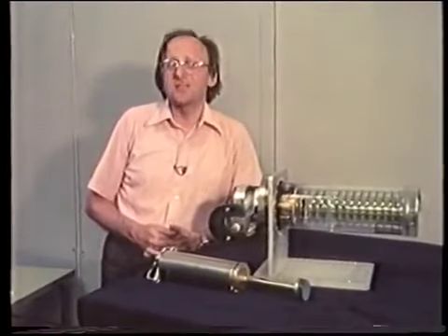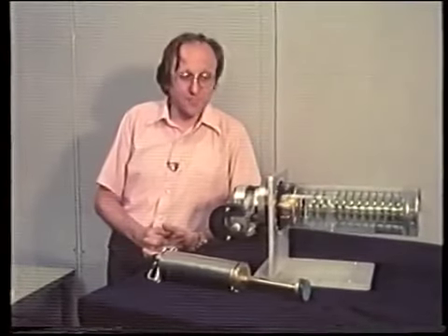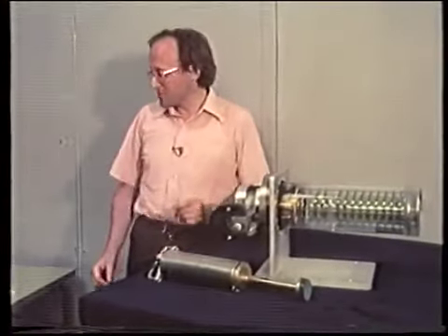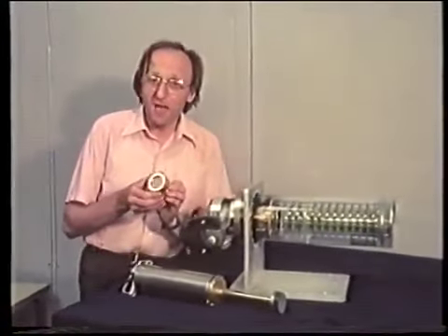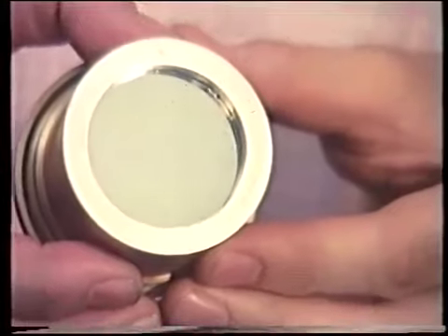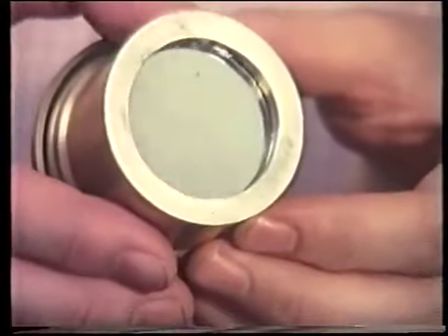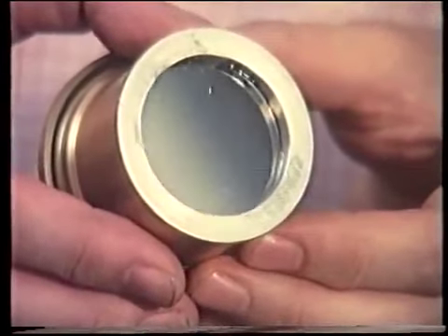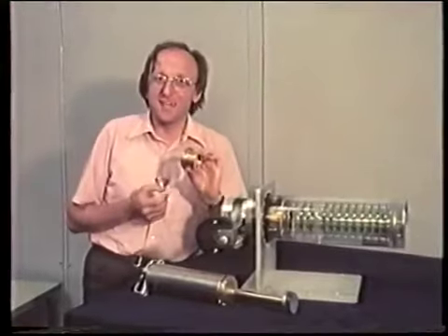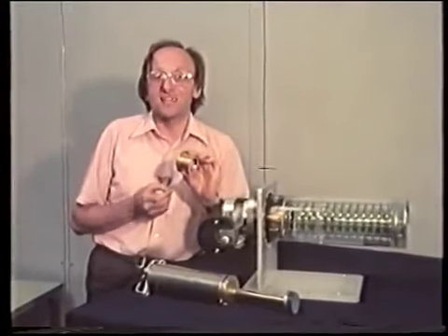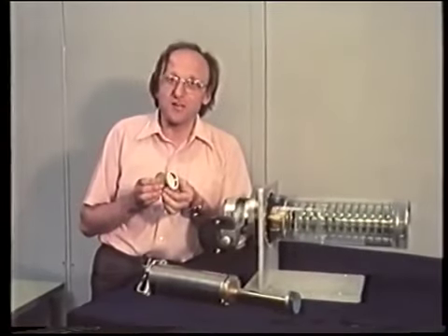Although the idea behind this camera is rather easy, a great deal of effort has gone into getting the technology right. For example, the mica window. It's only 4 microns thick. Now, that is not sufficient to seriously degrade the resolution as the electrons travel through it to strike the emulsion, which is placed at the other side. In fact, it degrades it so little that resolutions of around 100 line pairs per millimeter are possible.